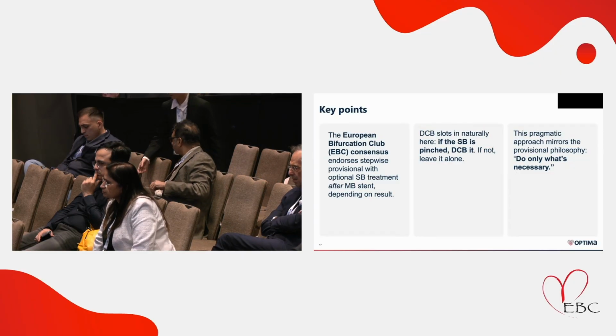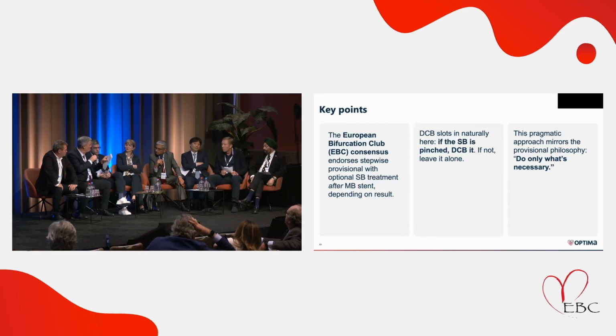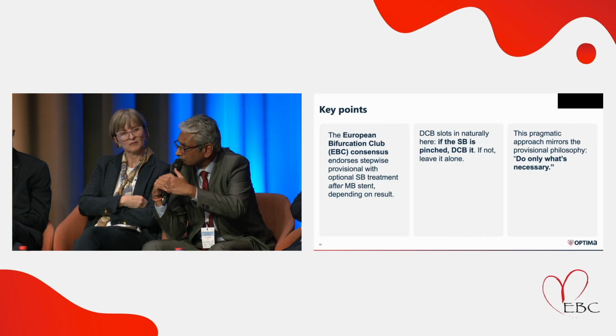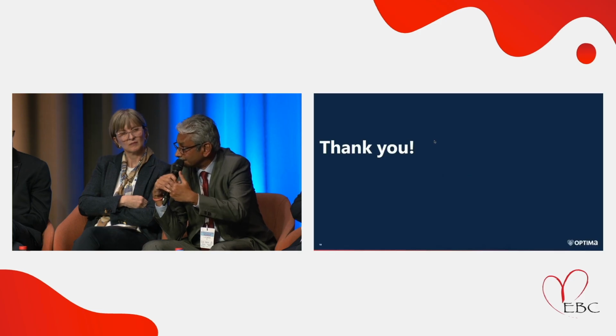Sudhir, there are some companies which put the drug before folding the balloon and some put it after folding. Does that make a difference? Yeah, it may make a difference, but the bench tests and some animal studies have shown that the amount of drug which is released into the tissue is about 20-30%, because some is lost in transit also. So you can't avoid that.